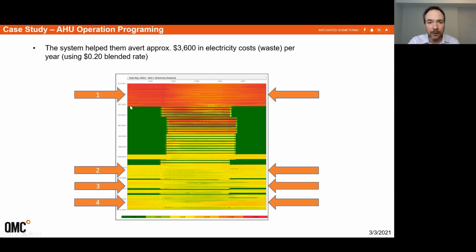At some point in early October, a service technician came in and set the on and off points of the handling unit closer to operating hours. So you can see it only came on at about 6 in the morning and was shutting off at about 6 at night. You can see these thin green lines on the heat map indicating weekend days, where it was completely shut off. So the system was operating the way it was expected to.